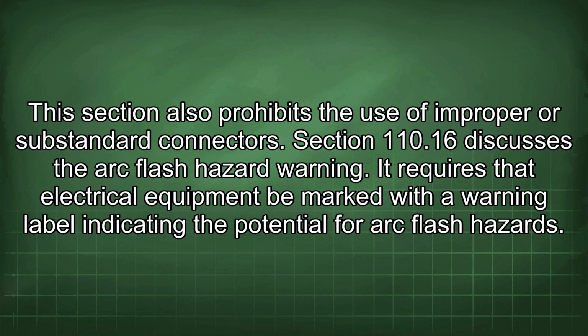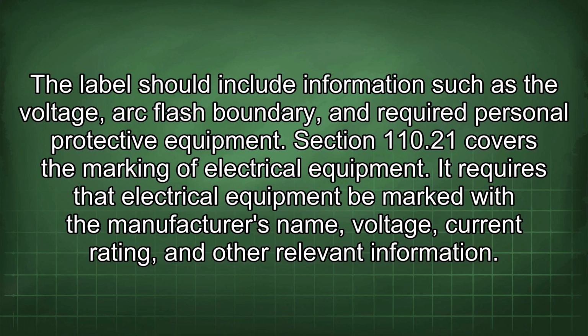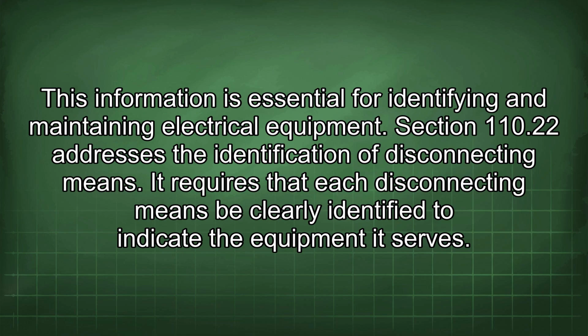Section 110.16 discusses the arc flash hazard warning. It requires that electrical equipment be marked with a warning label indicating the potential for arc flash hazards. The label should include information such as the voltage, arc flash boundary, and required personal protective equipment. Section 110.21 covers the marking of electrical equipment. It requires that electrical equipment be marked with the manufacturer's name, voltage, current rating, and other relevant information. This information is essential for identifying and maintaining electrical equipment.